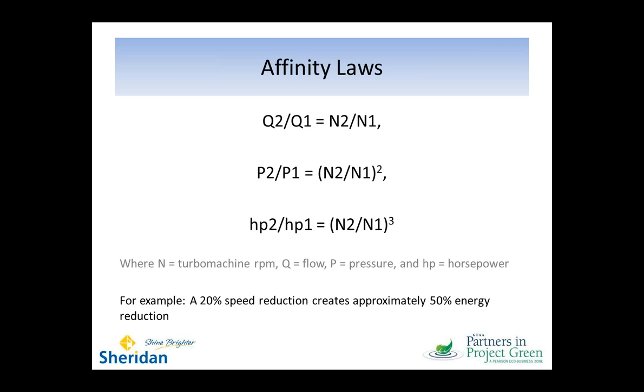Why do we care about variable speed drives? What makes them so attractive? Well, really, it comes down to these affinity laws that I'm presenting here. And they're not even really laws. They're sort of affinity rules. But here's what they tell us. If I change my motor speed, in this case represented by N, by half, for example, I should expect my flow to reduce by half, and that's what the first equation is telling me, that the proportion of change in speed is the proportion of change in flow.